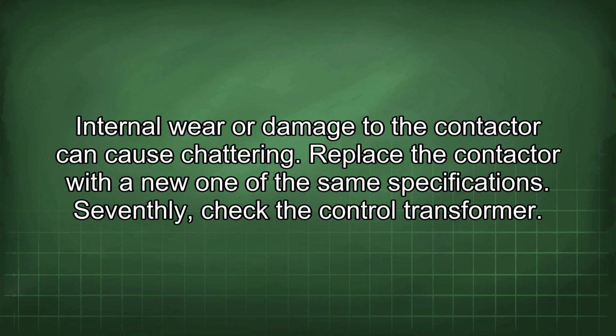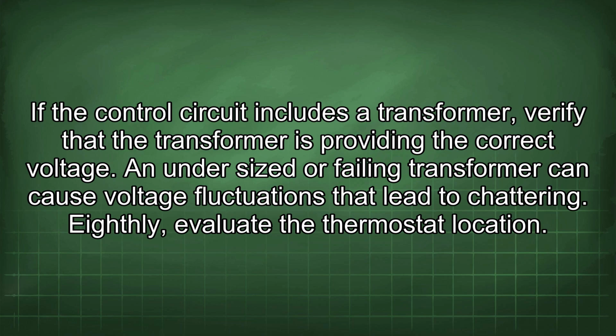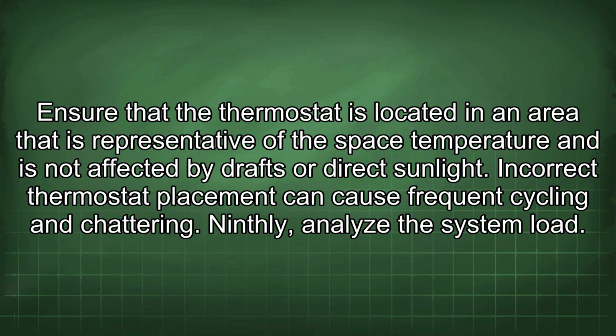Seventhly, check the control transformer. If the control circuit includes a transformer, verify that the transformer is providing the correct voltage. An undersized or failing transformer can cause voltage fluctuations that lead to chattering. Eighthly, evaluate the thermostat location. Ensure that the thermostat is located in an area that is representative of the space temperature and is not affected by drafts or direct sunlight. Incorrect thermostat placement can cause frequent cycling and chattering.